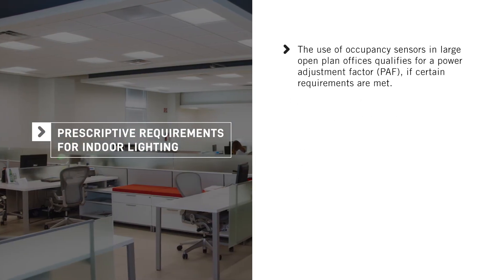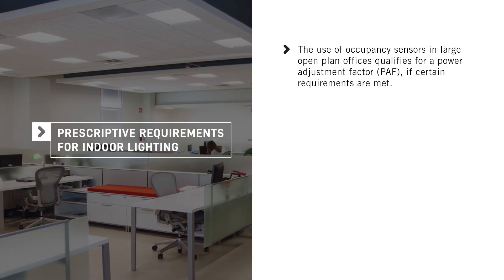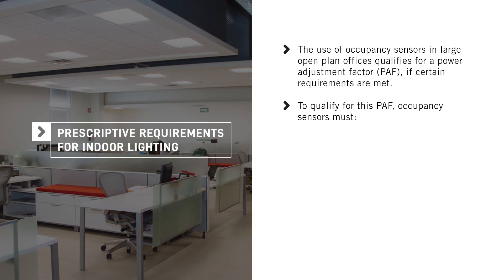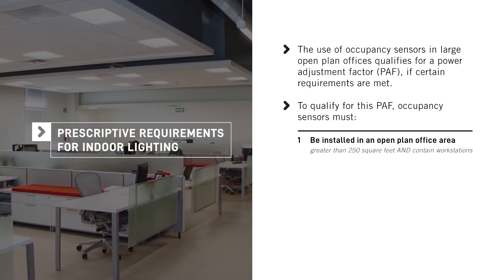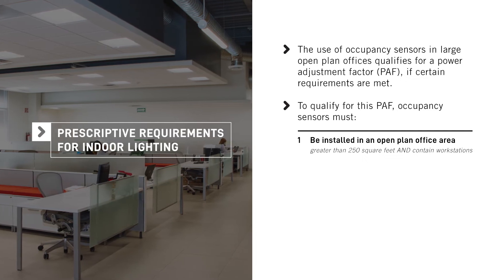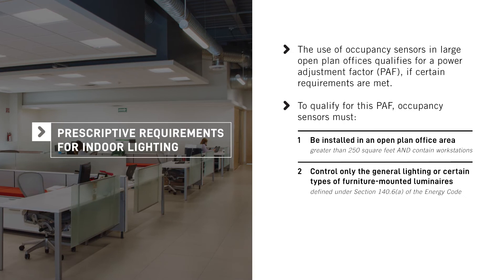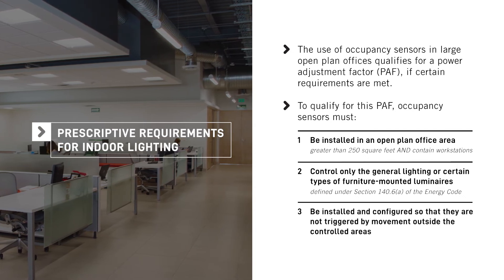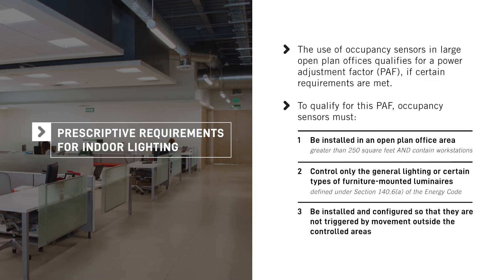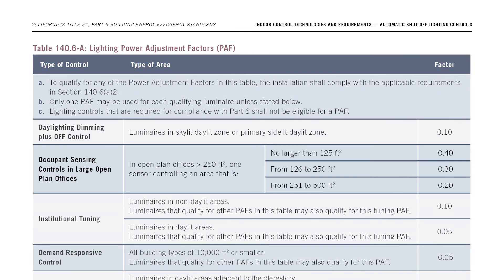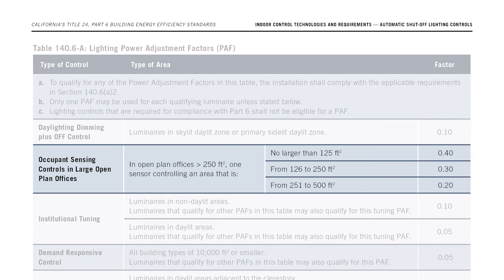Second, the use of occupancy sensors in large open plan offices qualifies for a power adjustment factor (PAF) if certain requirements are met. To qualify, occupancy sensors must be installed in an open plan office area greater than 250 square feet that contains workstations, control only the general lighting or certain types of furniture-mounted luminaires defined under Section 140.6(a), and be installed and configured so they are not triggered by movement outside the controlled areas. When all these conditions are met, the system qualifies for a PAF between 0.2 and 0.4, depending on the size of the occupancy sensor control zone per Table 140.6-A.